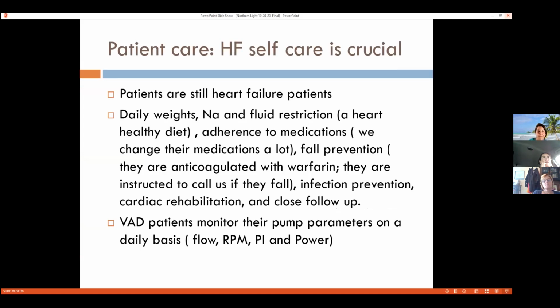What I have here is a simulation pump that we use for teaching. This is the controller, the pocket controller. You can see there are two power cords, and right here, this is the drive line. It's pretty hard to get the drive line out, but it can be done. If you open this and push down this red button hard and pull on this really hard, you will get a red alarm. It's pretty darn loud, right? And the pump stops because it's literally not connected to anything at all.